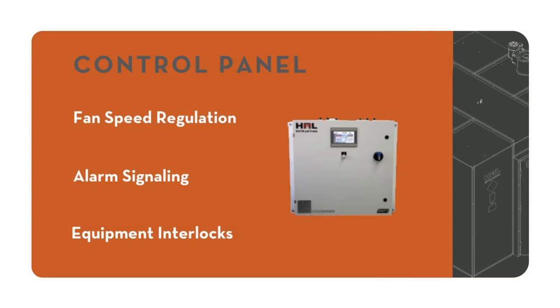And with that fire panel interlock, if your fire suppression system goes off, you can have the control panel send a signal to your building fire alarm. And that building fire alarm will send a signal to your fire department, and then they can come on site. So that is, again, dependent on your jurisdiction. Some might require it and some might not.